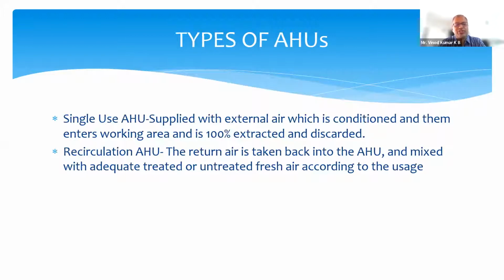Accordingly, your fresh air intake into the air handlers is modulated to meet the requirements of the air control in the respective area. So we call them recirculating AHUs, where return air is taken back to the AHU, which is then mixed with a percentage of fresh air, and then it gets cooled and treated. It goes into the space, which is the OT or the ICU. So this is what we generally see nowadays with a kind of AHU. We call it a recirculation AHU, which has an arrangement of fresh air coming into the AHU and then it gets into the system.